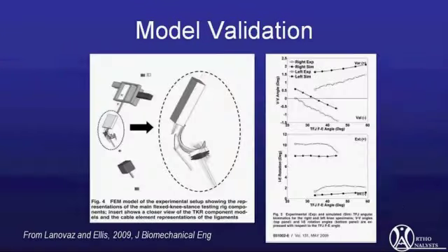Next slide, please. I thought I'd highlight just a couple of these. This is from a Canadian group. It basically shows an explicit finite element model of a knee simulator rig, sort of a more lower limb type rig. And this took the next step to predict simultaneously both kinematics for the patellofemoral joint as well as the tibiofemoral joint. And you can see on the right some comparisons of kinematic predictions with the experimental cadaveric measurements, and you can see reasonable model validation there.